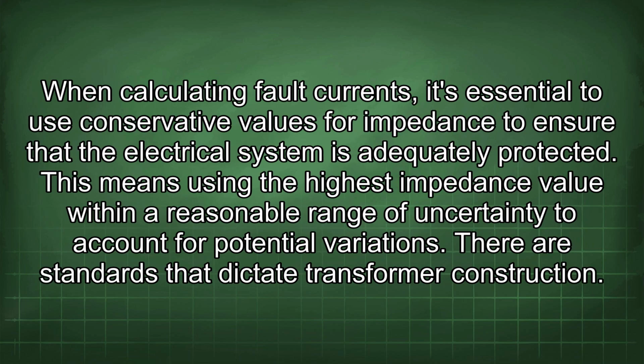When calculating fault currents, it's essential to use conservative values for impedance to ensure that the electrical system is adequately protected. This means using the highest impedance value within a reasonable range of uncertainty to account for potential variations. There are standards that dictate transformer construction.